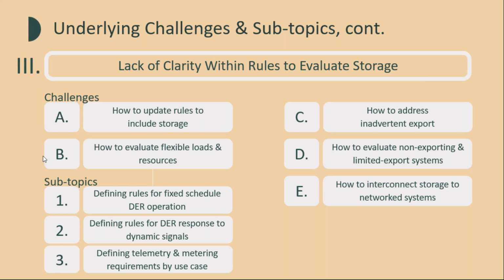Sure. This one is somewhat of a niche issue, but network systems do occur in downtown environments. If you're not familiar with them, network systems are basically different from the typical radial distribution feeder, where a feeder can be connected in multiple locations, usually through different substations. A downtown area can have a very flexible and resilient electricity system, so that if a fault occurs on a line, it can be isolated between two points very quickly, and very few customers would lose power rather than losing power all the way along a feeder.